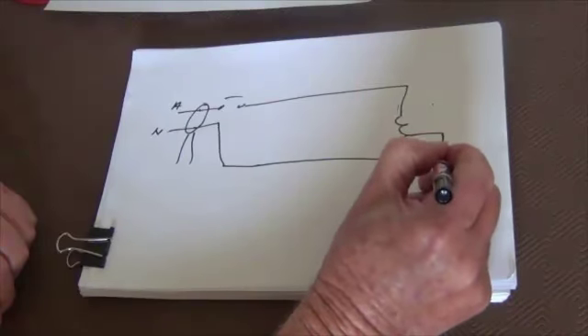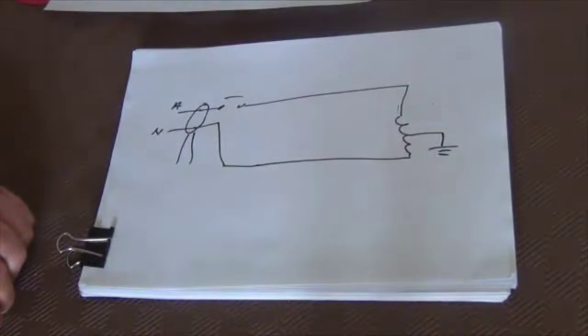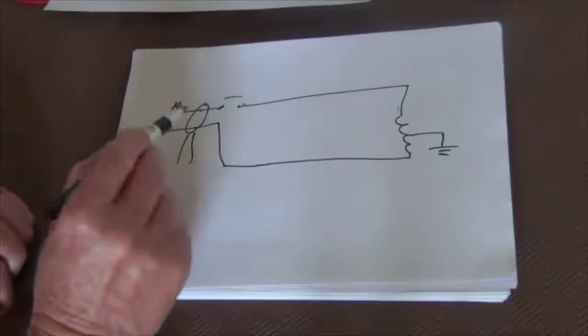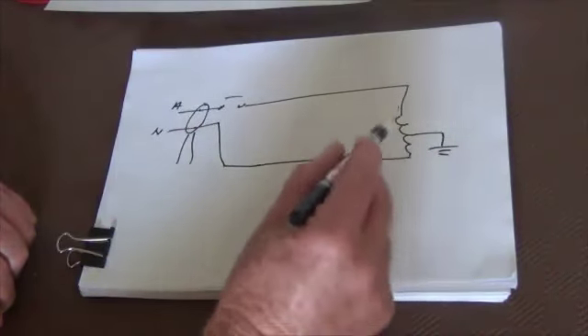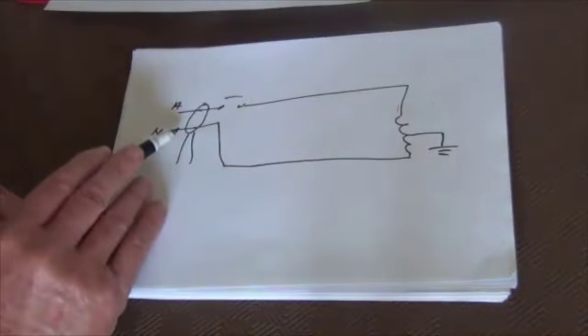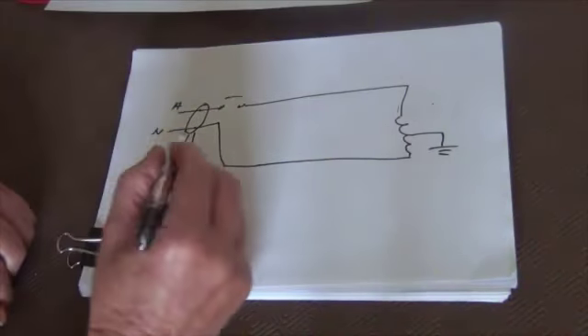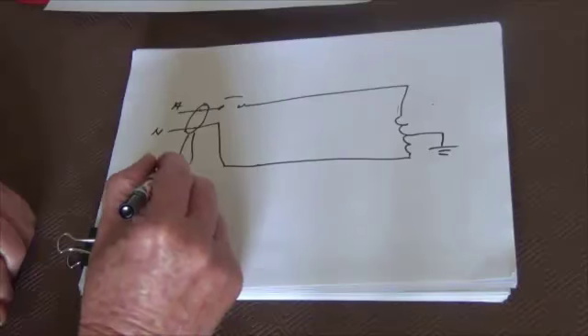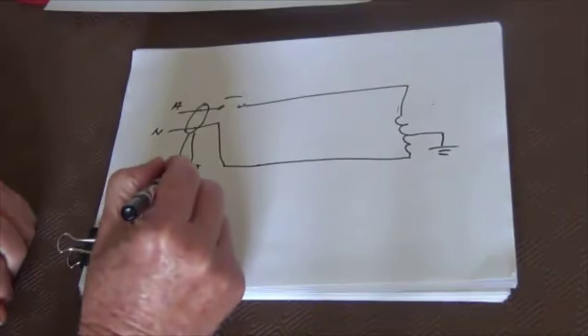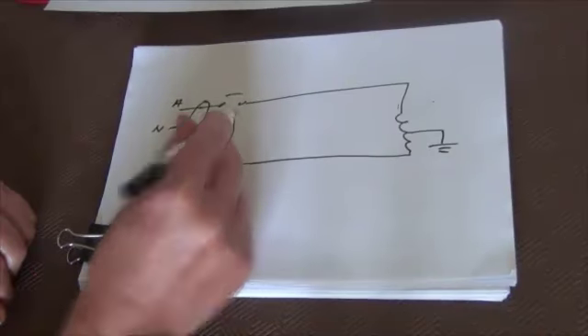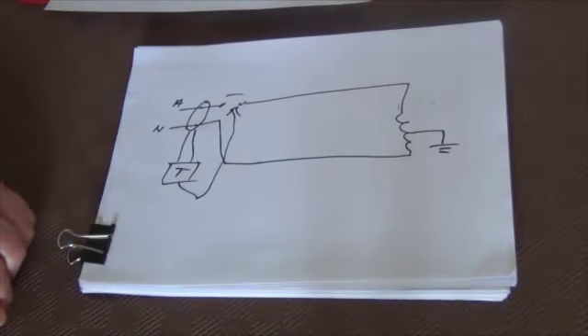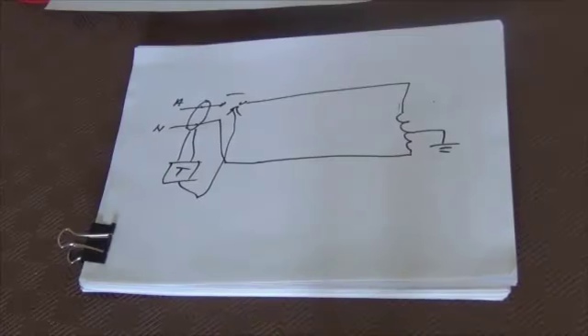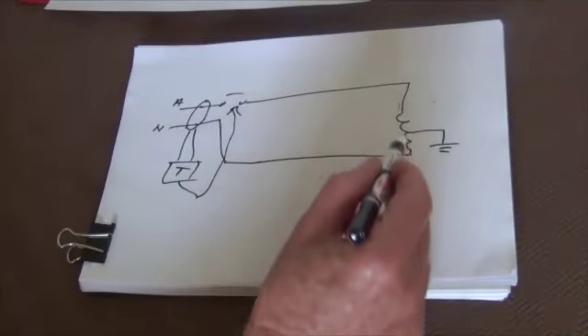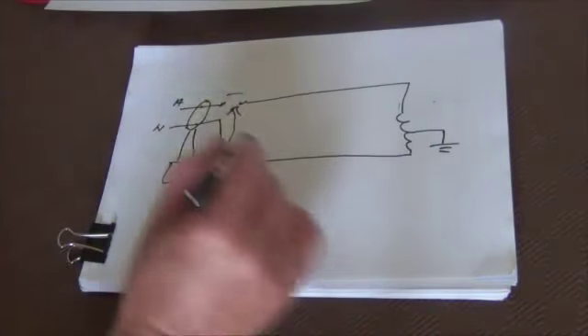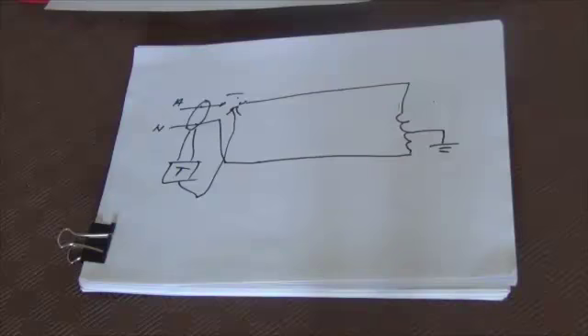But if somebody goes and touches the element and gets electrocuted, there is now current flowing through there, so there's less current coming back here. It creates an imbalance in that CT, which triggers a trip mechanism, which automatically opens the switch. And that is how an RCD works. It just measures the difference between the current going in and the current going out. If it's different, it trips the switch.